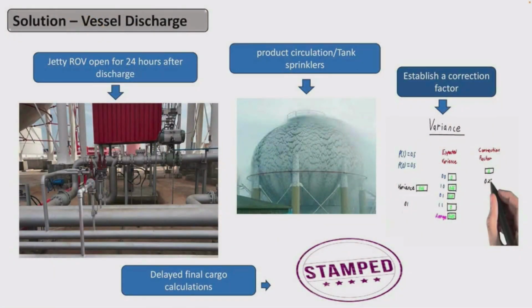For vessel discharge, here's the solution we looked at. After the vessel discharge operation, we close our jetty manifold, the manual valve. But the ROV connected to the flow meter, we leave it open for at least 24 hours, because after receiving the product into your tanks, you must blow your line. And then you definitely have a non-return valve, so nothing comes back. In that phase, you just have a vapor phase.